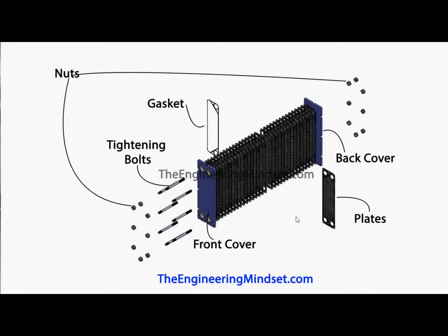So we've got the end plates here, or the front and back cover, made usually from mild steel, and they're very strong. They're there to hold everything together. Then we've got the nuts, which attach and tighten onto the tightening bolts. The tightening bolts fit in some grooves and run the entire length of the heat exchanger. The bolts are tightened, and that compresses all the plates together and squeezes the gaskets against the plates to make the heat exchanger completely waterproof or leak proof.